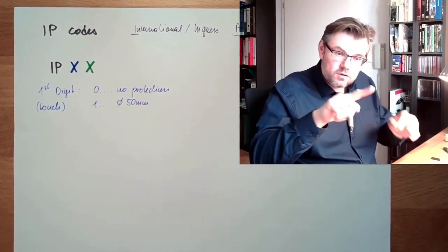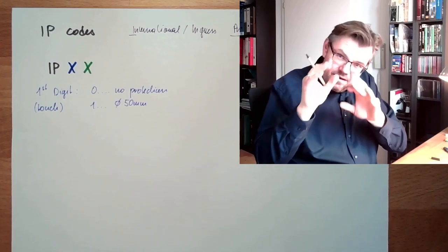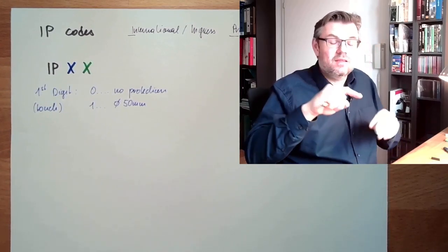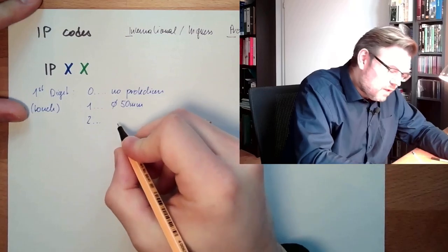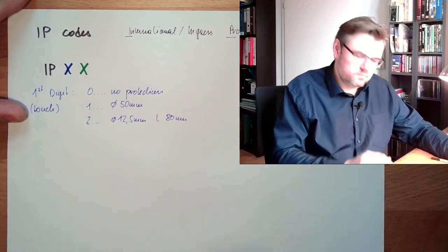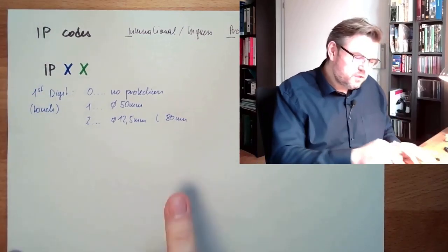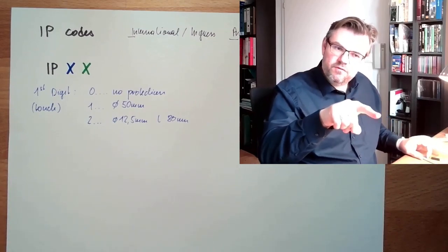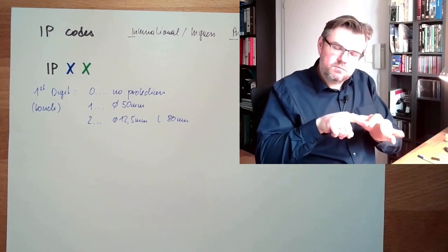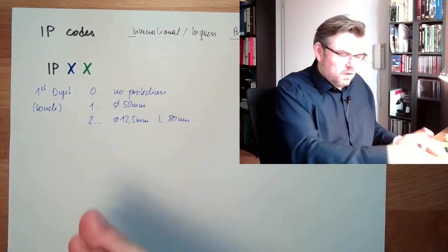With the finger, not. Because the finger is thinner than, usually the fingers are thinner than 50 mm. Then we would have IP protection code 2. This is 12.5 mm and a length of 80 mm. If something is thinner, I might touch it. If something is longer, I might touch it as well. Usually, this is protection against touching with the finger because the finger is usually shorter than this 8 cm and broader than this 12.5 mm.